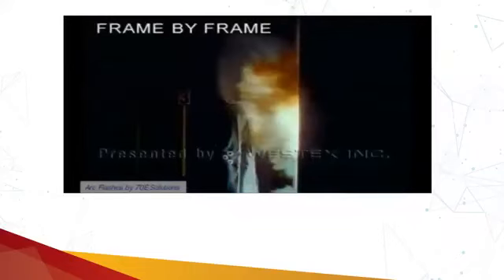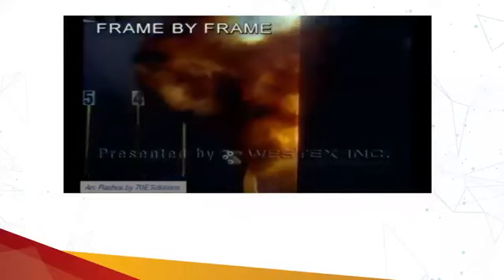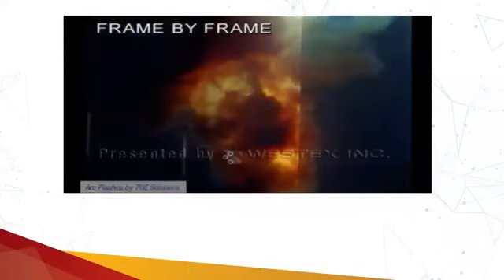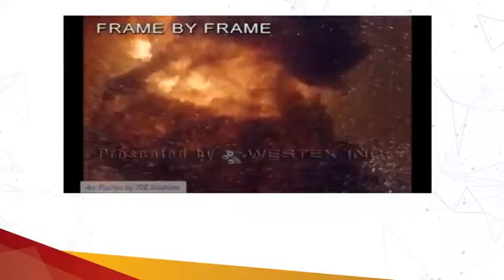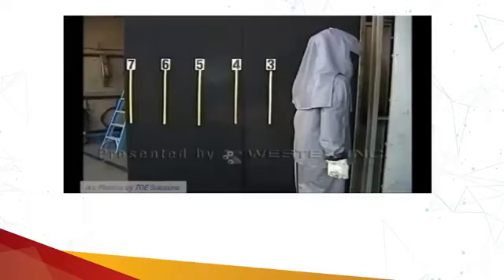Frame by frame, once again, you can see the arc clearly leave the motor control center and leap 4 or 5 feet out of the gap, envelop the mannequin, and continue to rocket out both up and down. Right. So if a person is working on the live system, and it's justified and authorized work, and he's wearing the right personal protective equipment, then it can save a life.